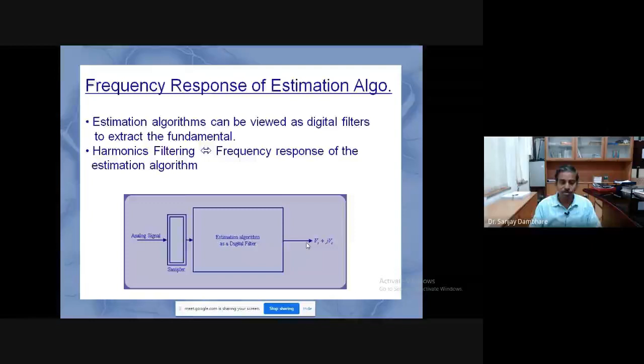Then after estimating the fundamental frequency in the relays, the relay takes the fundamental phases and fundamental values, and appropriate values I will say, because there is a lot of things which can be estimated. So appropriate values of voltage or frequency or current are estimated, and the angle is also estimated. And then the relay takes a decision, and then it gives it to the circuit breaker.